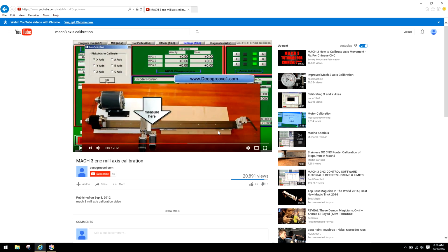The other thing you want to look at is the distance you want to measure from. If you want to measure from right here, let's say where I'm moving right now, you can see the cursor actually moving up and down. That's a very short measurement. Let's just say that's 2 inches. If you wanted to measure from a 2-inch travel, that's fine. But in essence, if this is 10 inches, for instance, the most accurate way would be to measure the movement at the longest range. This way you know what your variable would be at the longest range of the table to give you the most accuracy. Now, what does that mean? Well, let's think about it for a minute.